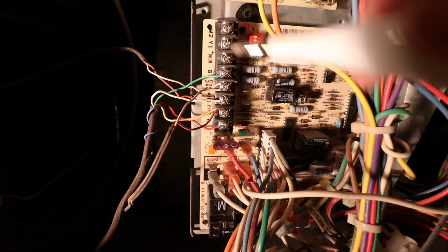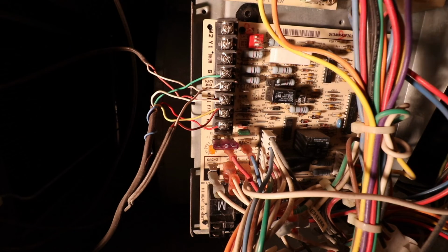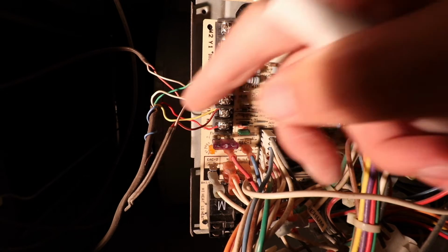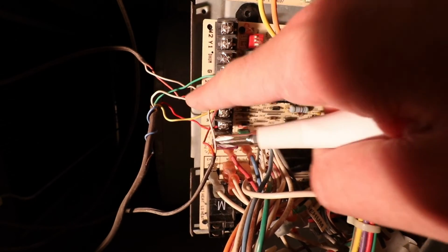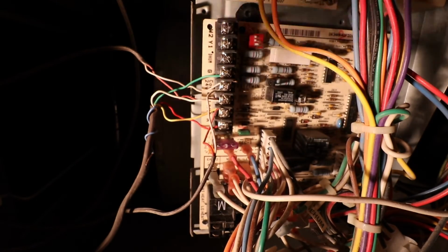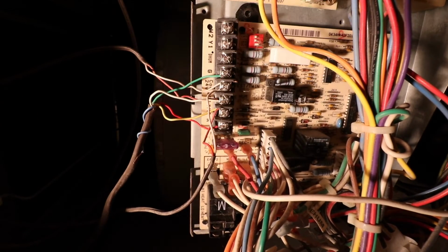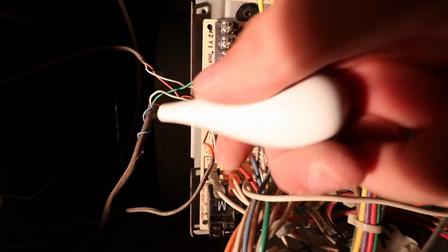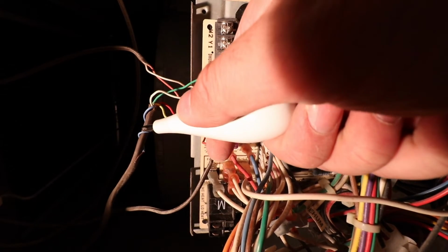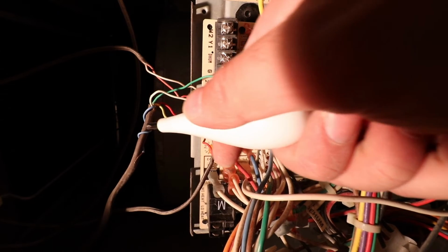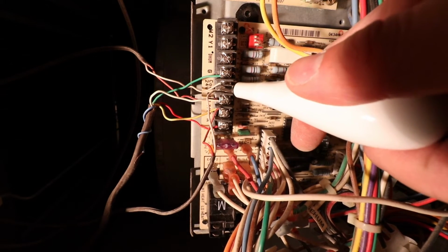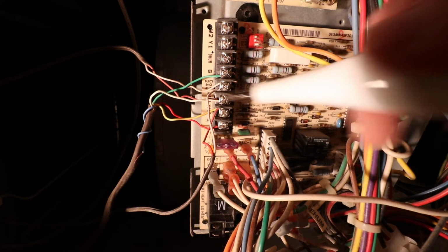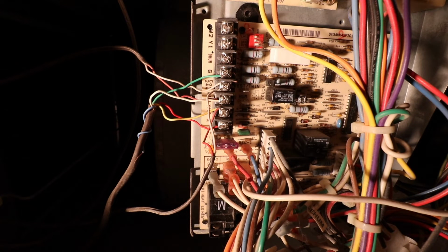And we've got a couple different wires here, and we want to identify the right wires that we're going to change around. So what we've got are 2 wires here, 2 wires here, and then we have our bundle of 4 wires here. And this is the one that we need to identify. These are the wires that are going to the thermostat. Now you can see on this bundle of wire, we actually have an additional wire right here, this blue wire. So we could just connect that to the common terminal, which is right here. And then we could go ahead and connect that to the common terminal up at the thermostat, and we would now have a common wire.